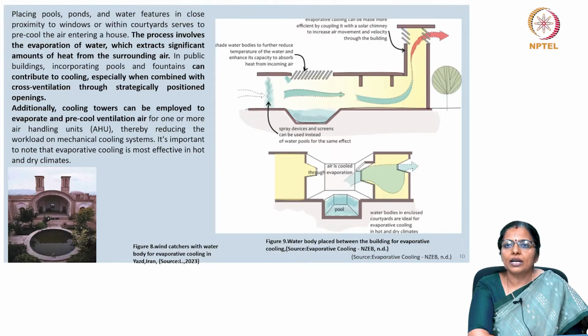Additionally, cooling towers can be employed to evaporate and pre-cool ventilation air for one or more air handling units, reducing the workload on mechanical cooling systems. Evaporative cooling is most effective in hot and dry climates, because in warm and humid climates the air is already moist, and adding more moisture will only increase discomfort unless handled prudently.